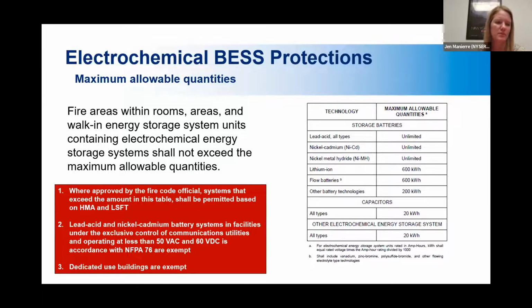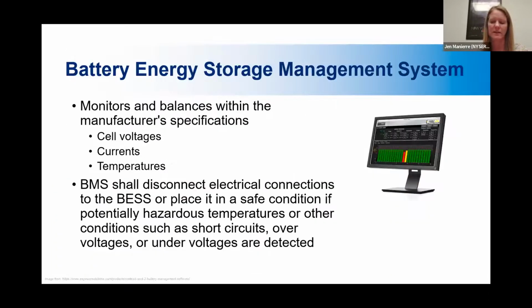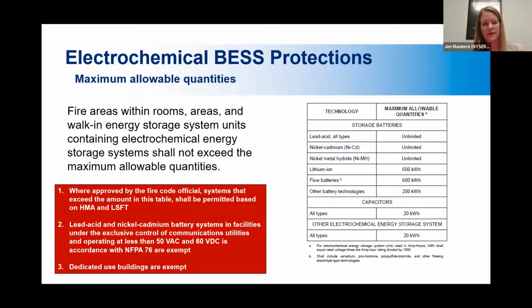Number 2 here in the red box on the screen is very common for lead acid and nickel cadmium battery systems and facilities that are under the exclusive control of communications utilities. They have a lot of exceptions throughout the code, and I couldn't tell you the very scientific reasons why. I'm not a battery engineer, but I know that communications utilities have been having these large battery backup systems for many years, and they seem to have a decent track record. And I have to imagine that that comes into play for why they have this exception throughout the code.